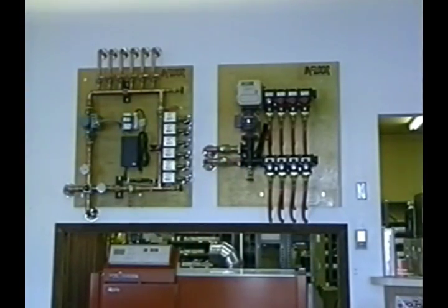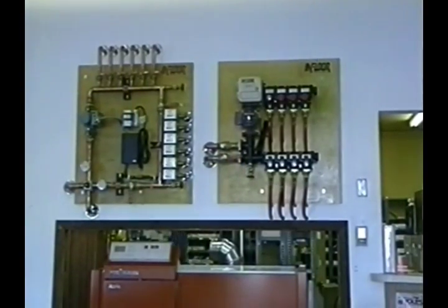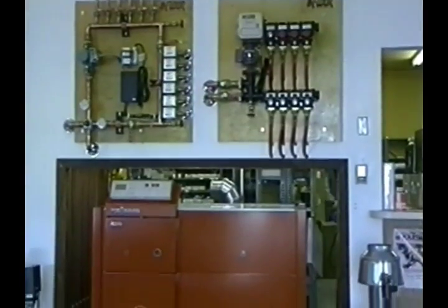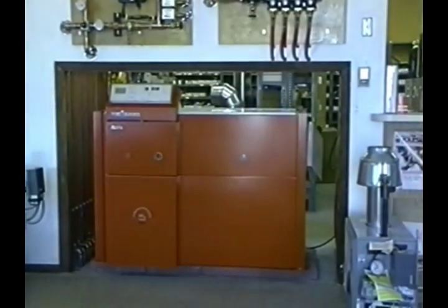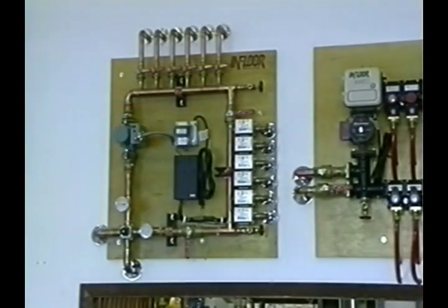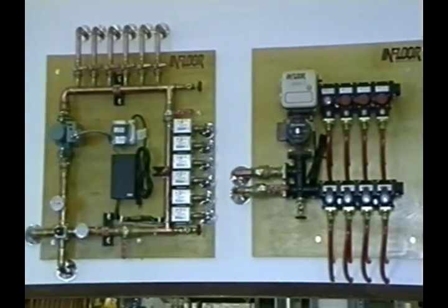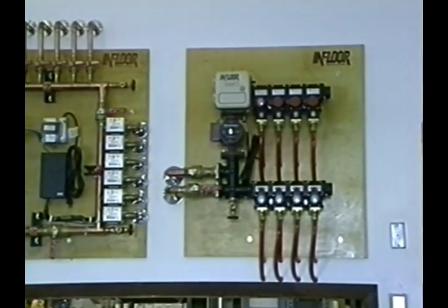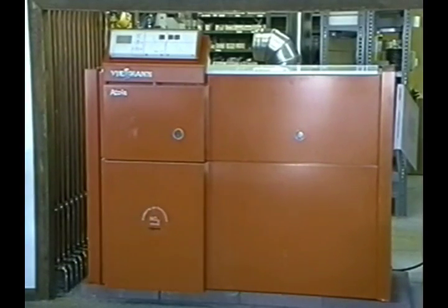When your in-floor heating system was first designed, the boiler type was determined based on location of the boiler room, venting access, and budget. To begin your boiler room setup, set the boiler in place, keeping in mind the clearances required by both local codes and the boiler manufacturer. Make sure an electrical outlet is placed in the boiler area, along with a gas line to supply the boiler with fuel. It's recommended that the boiler be put on its own circuit breaker for maintenance purposes.